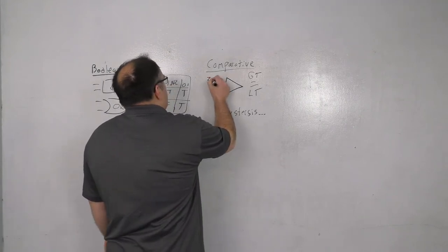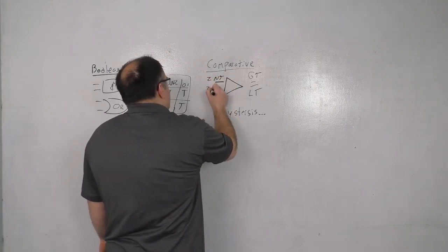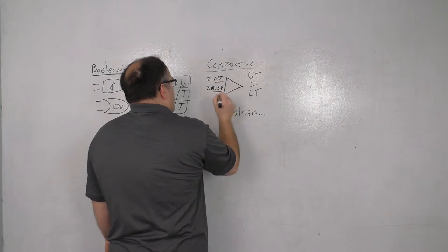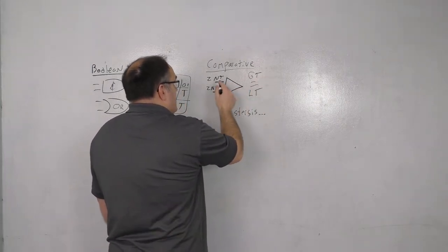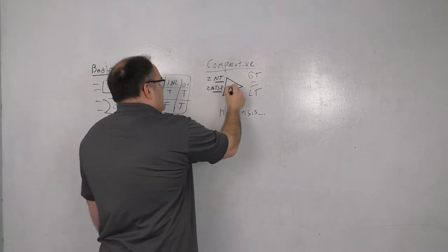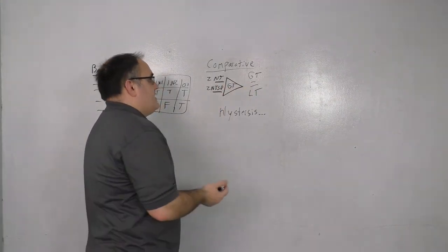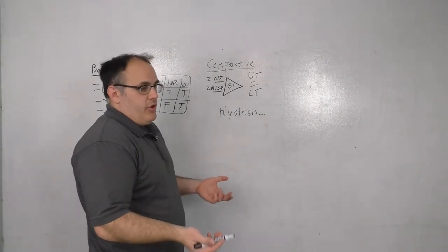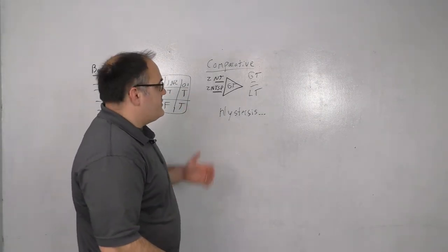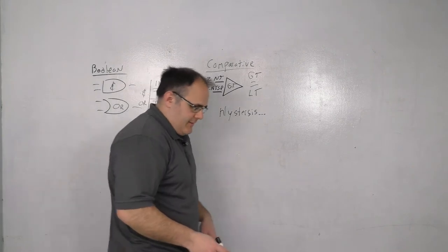So this would be zone temp and then zone temp set point. It would compare the two, greater than, less than. Let's say this is greater than. If zone temperature is greater than zone temp set point, then we want to enable our cooling PID loop. So that would be comparative blocks.